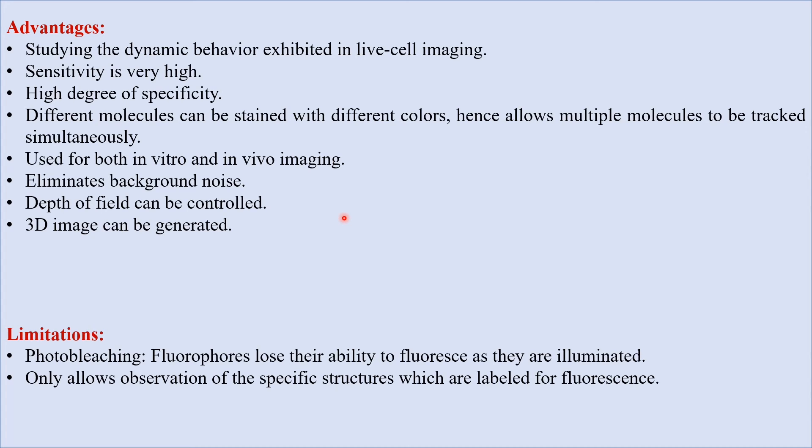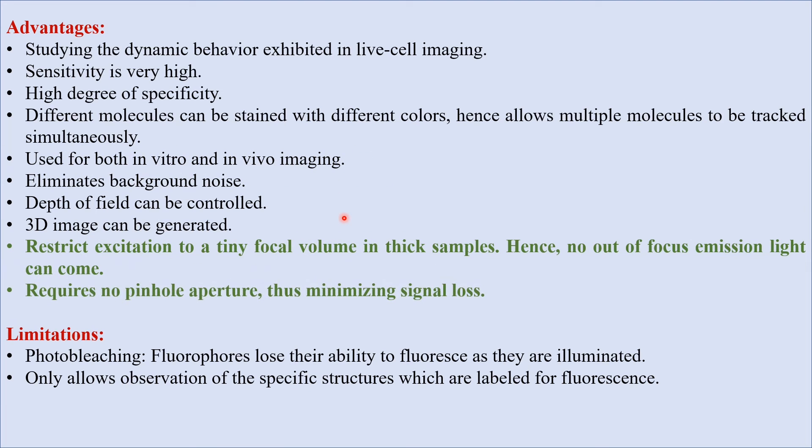Using two photon microscope gives some advantages over one photon microscope. Two photon microscope restricts excitation to a tiny focal volume in thick samples. Hence, no out of focus emission light can come. Two photon microscope requires no pinhole aperture, thus minimizing signal loss. It can reduce damage to the cells.